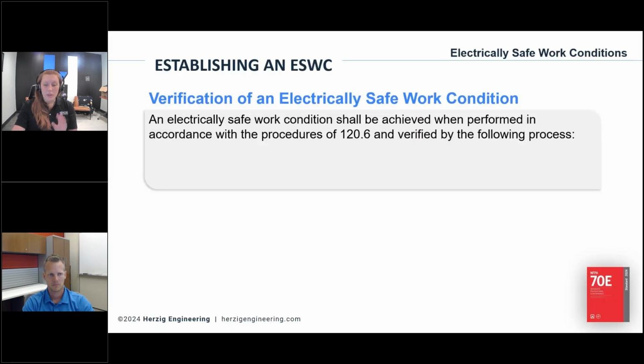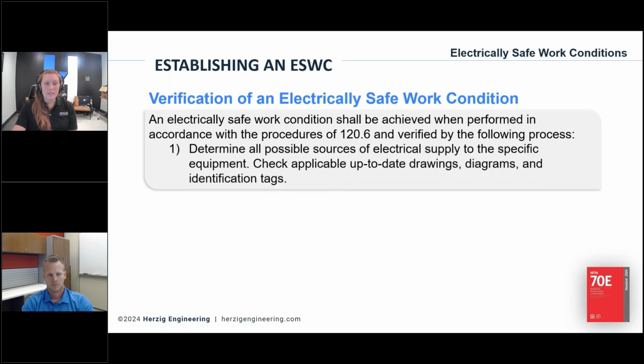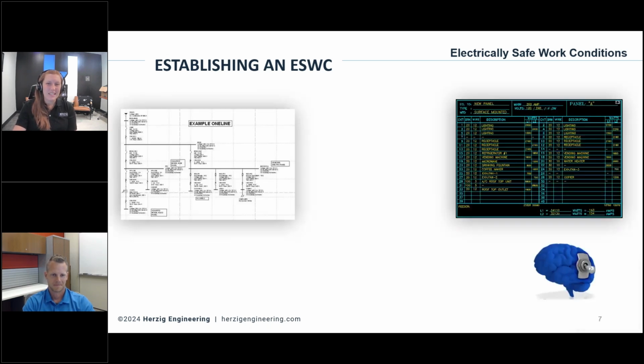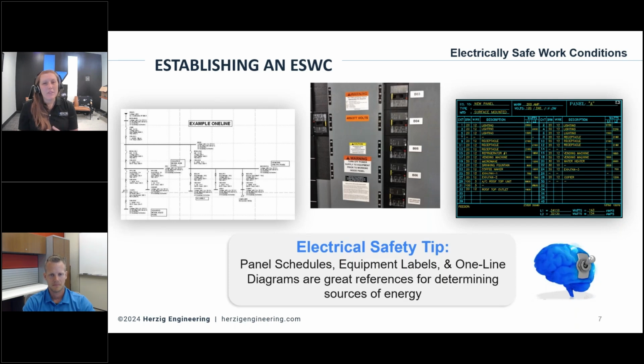Okay, so we're looking at Article 120.6. Let's dive in. First is just determine all possible sources. Figure out where the power is coming from, which is kind of like a no duh. If you're going to shut it off, you have to know where to shut off the disconnect switch.